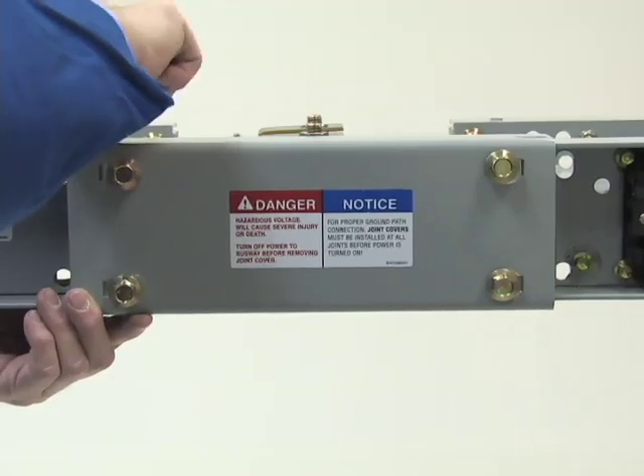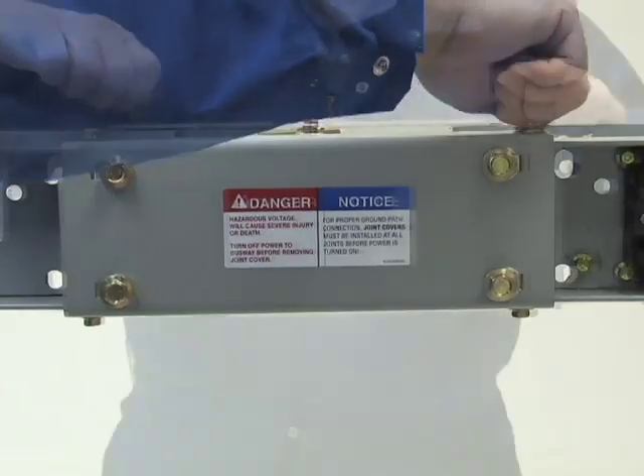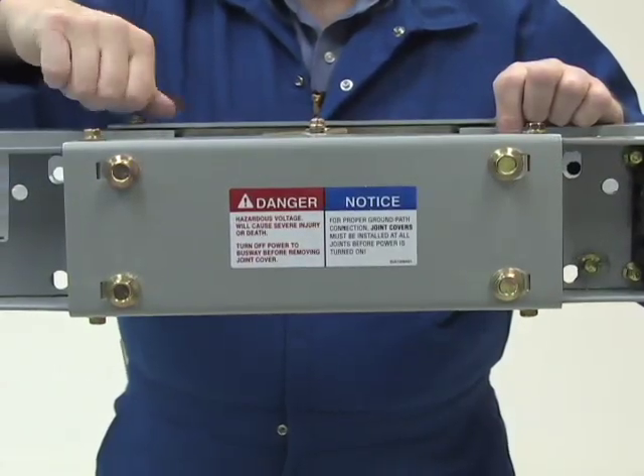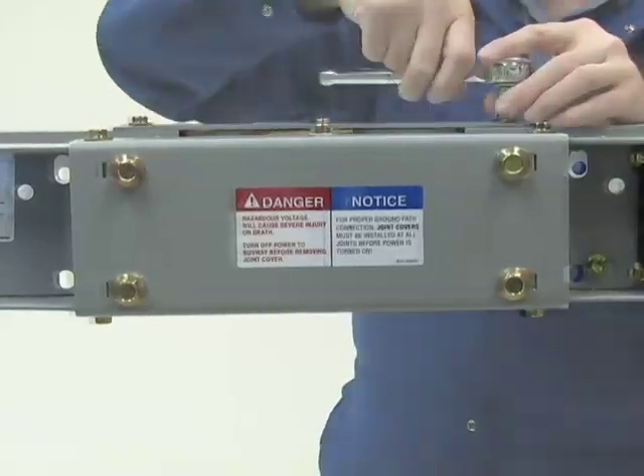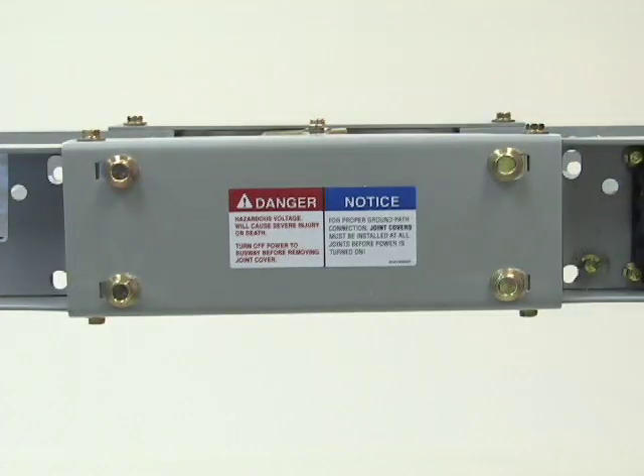Install the hardware through the slots on the top and bottom flanges of the joint cover. Repeat for the joint cover on the opposite side. Securely tighten all hardware to joint covers. You have successfully performed a joint installation of 2 sections of Eaton Cutler-Hammer Pow-R-Way III busway.